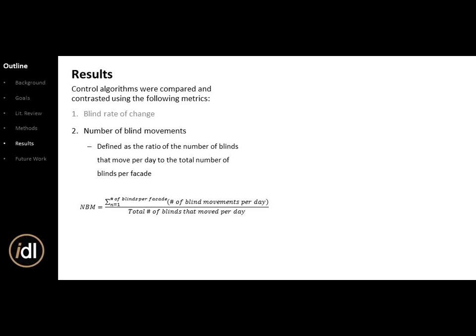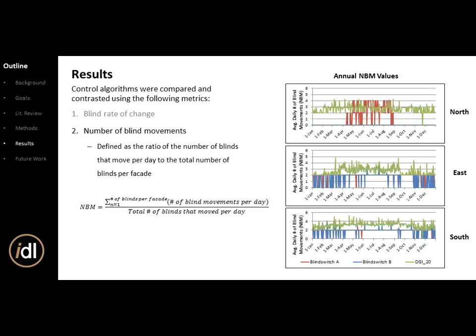Number of blind movements is the ratio of number of times blinds move per day compared to the total number of blinds per facade — opening and closing each count as one movement. DGI again has the highest number of blind movements. For Blind Switch A and B, on the east and south facade, you typically see a constant value of about two movements — blinds closing in the morning and retracting in the afternoon. In summer it's typically just closed in the morning and open in the afternoon.